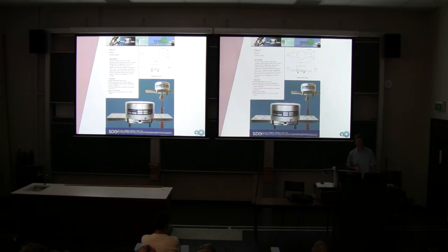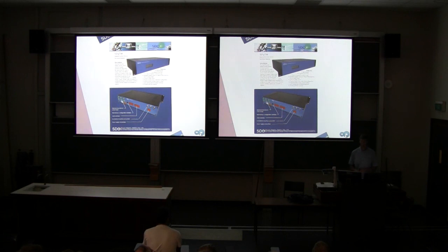But we are contending against conventional CTs that claim a lifetime of 40 years, so they really don't want to go up and take these out of service. The electronics, on the other hand, it's very difficult to make any electronic box with more than a 10-year lifetime. But because this is in the control room where you have access to it, and you don't have to take the entire network out of service, that's acceptable.